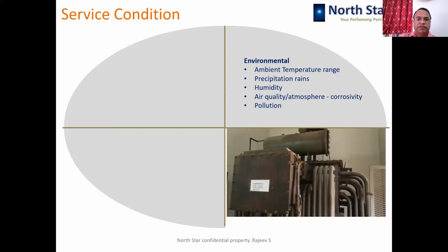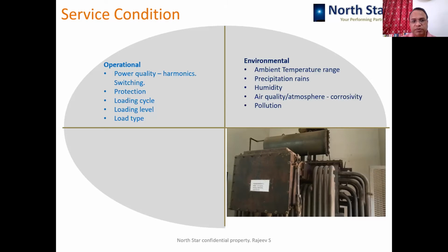Service condition means under which circumstances the transformer is being put into use. First is environmental. What is the temperature range over there? What are the weather conditions? How much rain is happening? What is the air quality? What is the atmosphere? Corrosivity of the atmosphere, pollution level of the atmosphere. That affects the transformer performance. Then operational aspects like power quality, for example, harmonics percentage in the incoming power, switching activities, switching levels, the kind of protection being provided, whether the loading cycle is being respected, loading level of the transformer, and what is the load type.